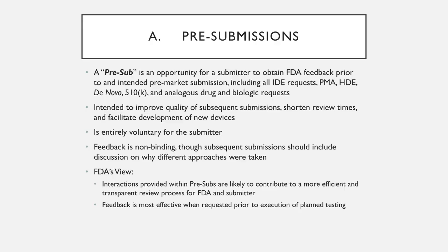Any misunderstandings result in lost time and lost money and a lot of failure of medical devices because of that lack of understanding. It's important to know that the pre-sub is entirely voluntary for the submitter. I would think it'd be naive to assume you could get away with not having to do this unless you had a robust history with a line of products already from that same company and you knew exact expectations based on your historical submissions with the regulatory body. For a brand new medical device startup, I almost would want to say that it'd be incredibly naive not to go through the pre-sub process.